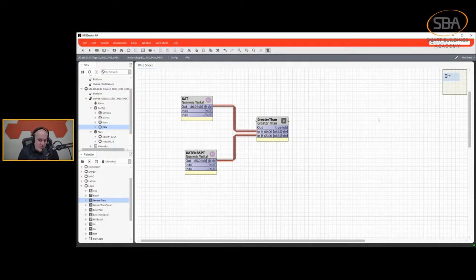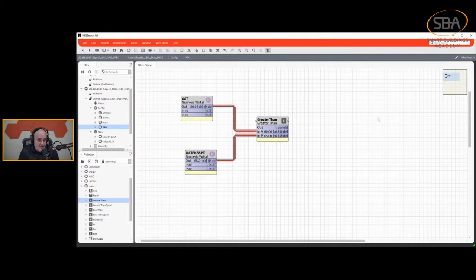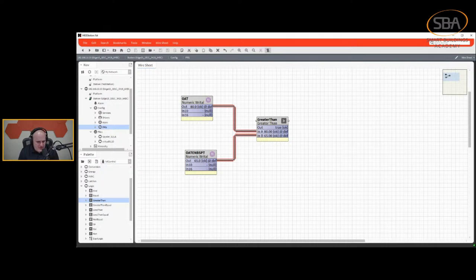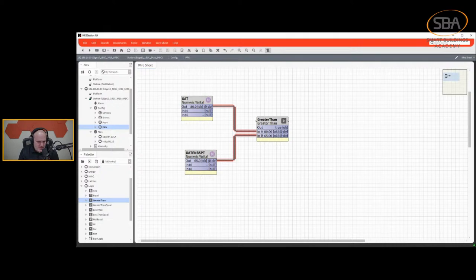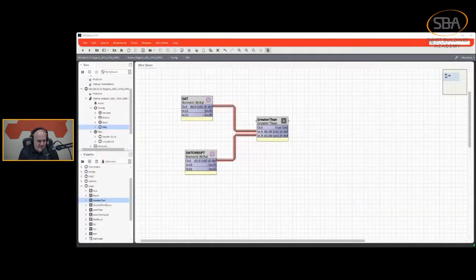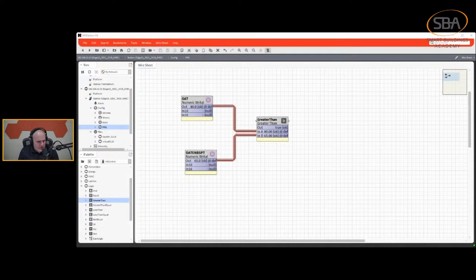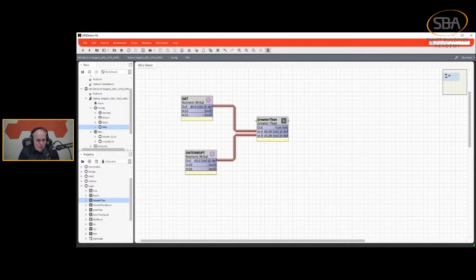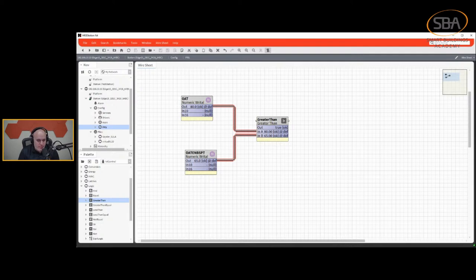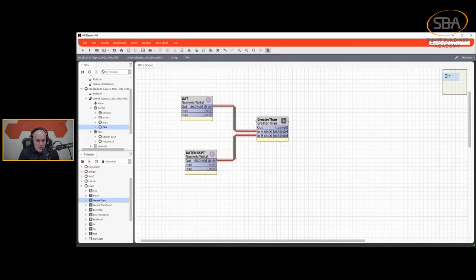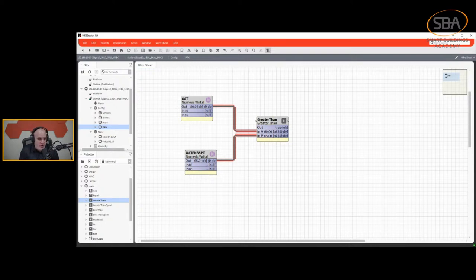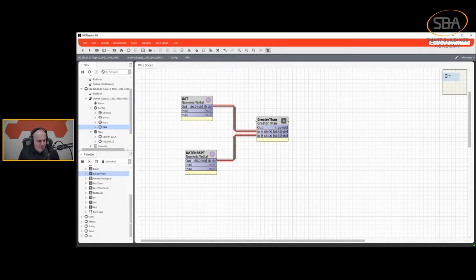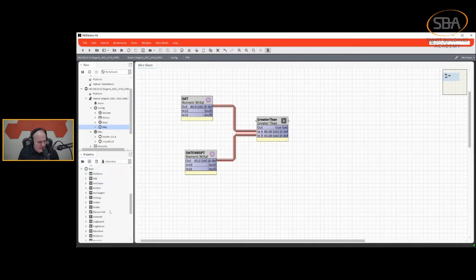But it's more than just that. You can do maybe trim and response. So we have a trim and response sequence, which we'll talk about guideline 36 on Friday. But with a trim and response sequence, we're going to go and with trim and response, you will go and look for calls for cooling or calls for heating. And when they exceed a certain amount over a time period, you will then gradually increase or decrease pressure setpoint, or maybe you'll increase or decrease temperature.